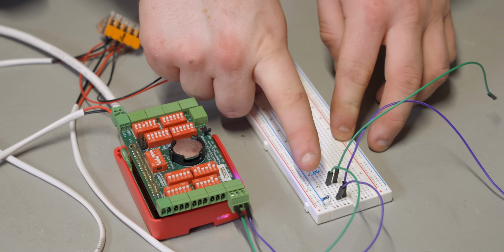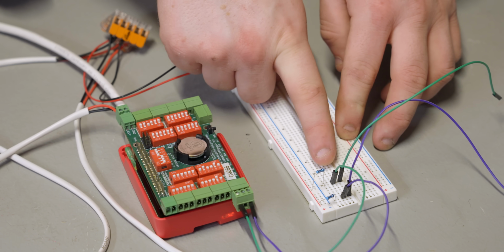In our case, we need to add something called a pull-up resistor, which makes sure that when there's no pulse being sent, the sensor reads a high signal, close to our voltage around 5 volts. If we didn't have that, the sensor wire could float between ground and 5 volts, which looks a lot like a pulse, which we don't want.